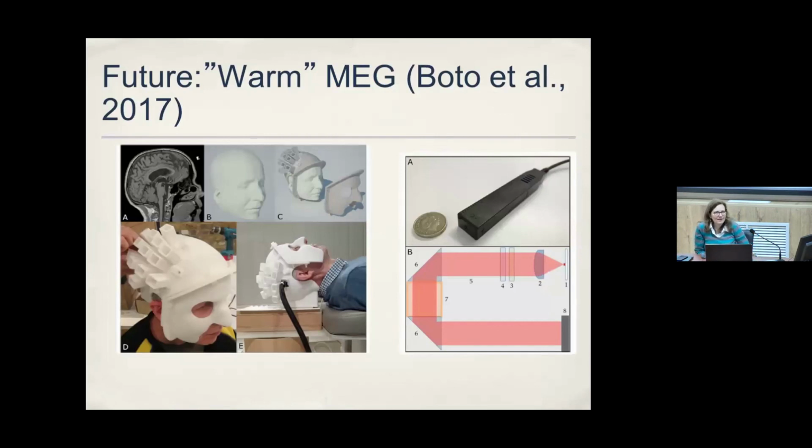It might be the future of MEG, because as I told you, though we didn't discuss it much, currently MEG is the best, as you understand, but it has a very bad disadvantage. It's money. It's very expensive. It's very expensive to build this magnetically shielded room. It's very expensive to build this device with the SQUIDs and all the sensor triplets. And moreover, it's very expensive to support this machine, because you have to have the liquid helium replaced every week to maintain the particular temperature where the sensors work, and it's the money, and you can't get rid of it.